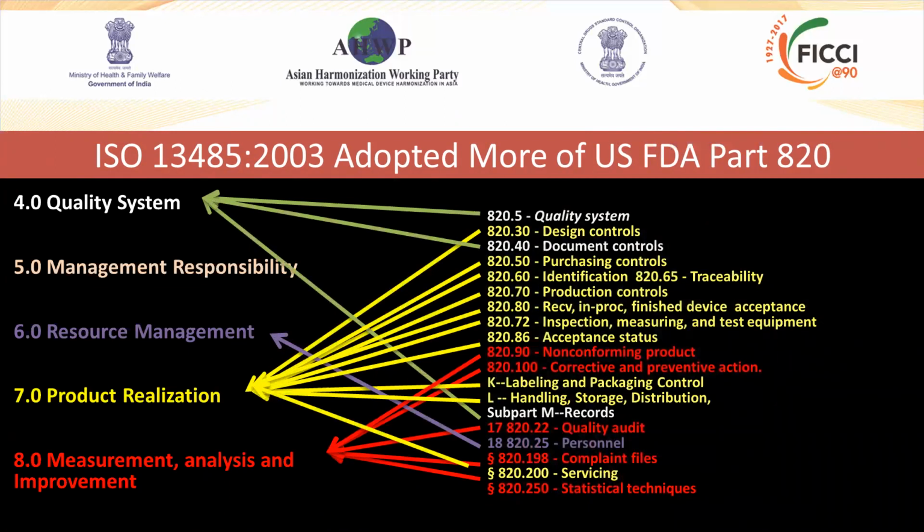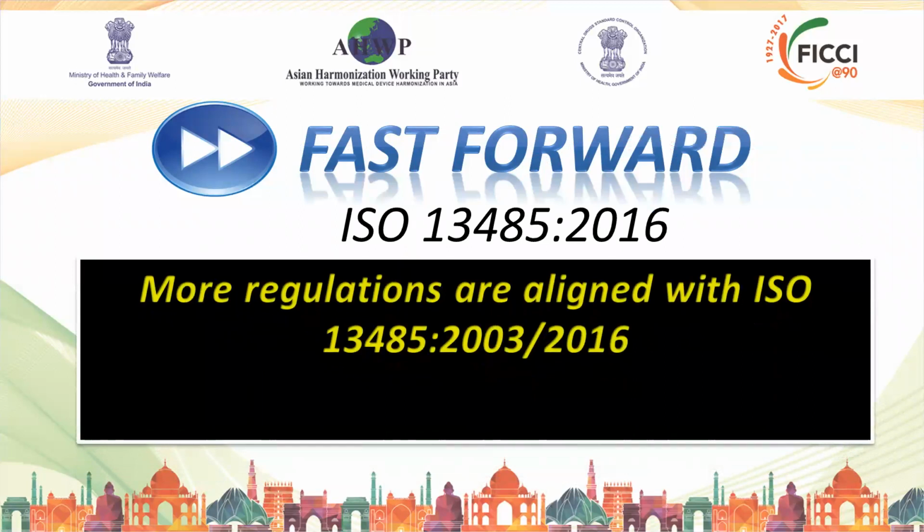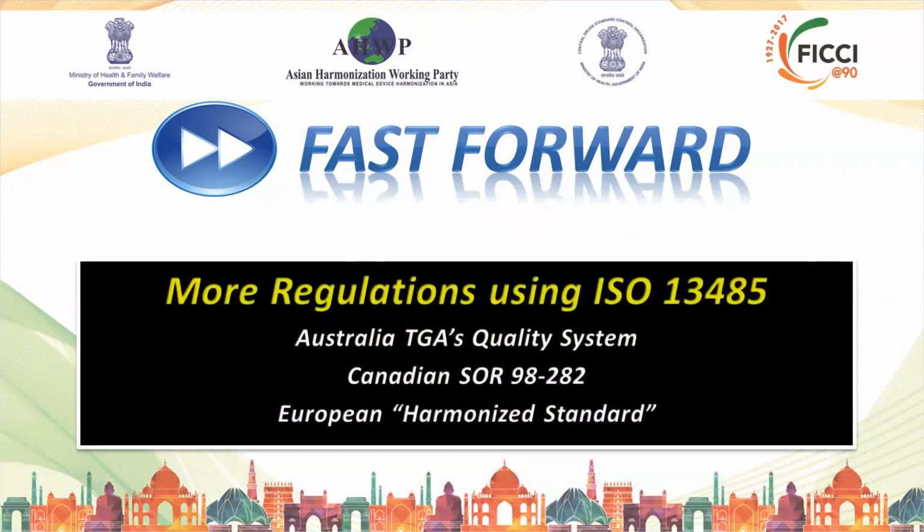We're going to fast forward here to the 2016 standard, and what we're seeing now is a lot more regulations, not just the US FDA, that are using 13485, especially the 2016 version, as it becomes a requirement. Some of the regulations that are most aligned with 13485 are the Korean good manufacturing practices and the Japanese as well, under their Ministerial Ordinance 169. One of the things you'll notice in the new 13485 standard is a lot more focus on regulatory compliance. So if you're selling into countries such as Australia, Canada, or the European Union, 13485 is a lot more relevant.